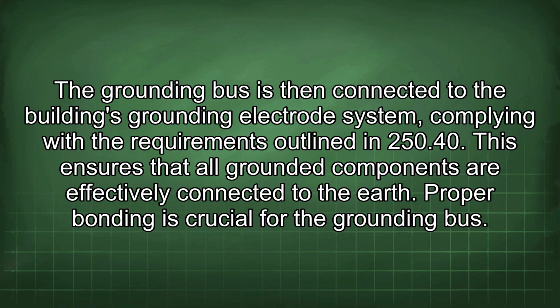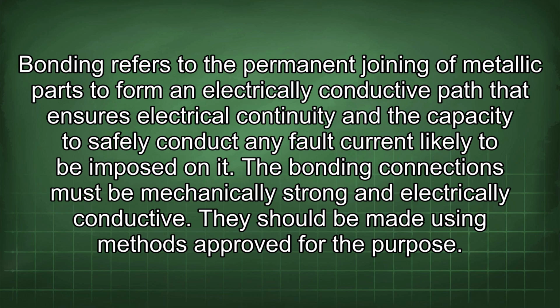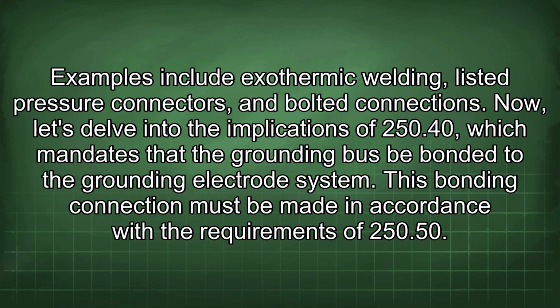Proper bonding is crucial for the grounding bus. Bonding refers to the permanent joining of metallic parts to form an electrically conductive path that ensures electrical continuity and the capacity to safely conduct any fault current likely to be imposed on it. The bonding connections must be mechanically strong and electrically conductive. They should be made using methods approved for the purpose. Examples include exothermic welding, listed pressure connectors, and bolted connections.